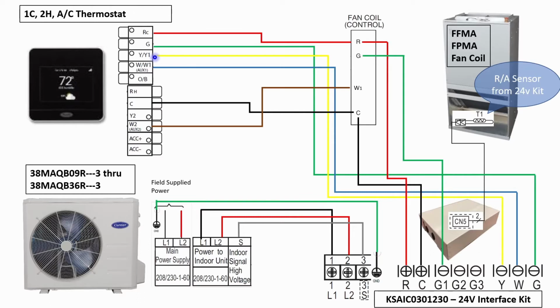Our thermostat is going to be set up conventionally, so we're going to use Y/Y1 on the thermostat and run that to Y on our interface kit. We're going to use W and go to W on our interface kit for heat pump heating. If your installation includes auxiliary heat, then you're going to use W2 on the thermostat, which is going to energize W1 on the fan coil, which will energize your electric heater as well.